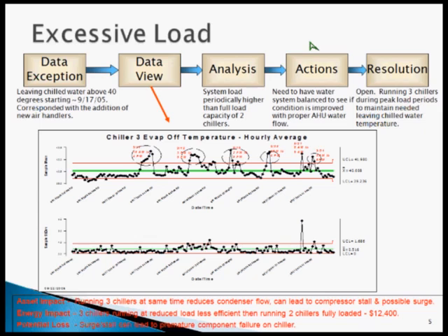Very inefficient. The demand went way up. There's a spike all of a sudden, a couple hundred kW. All of this was just an immediate response. We're coming in as energy engineers. We're saying, look, if we can keep those 2 chillers running, we're going to save energy. We're going to reduce wear and tear on the chillers. We're going to make sure we don't get the demand spike.